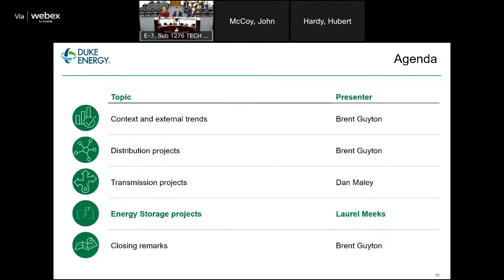Sure, great question. For high voltage circuit breaker applications, the industry standard still remains SF6. Duke Energy is very interested in exploring alternative technologies. Several vendors are starting to come out with commercially available options at the 115 kV and 100 kV voltage levels, and I've seen some up to the 145 kV class. But particularly at the 230 kV and 500 kV circuit breaker levels, there really isn't proven technology we've seen as an option to adopt. So the vast majority, the industry standard, still remains SF6 at this point, although we are interested in collaborating with industry on future opportunities to move away from it.